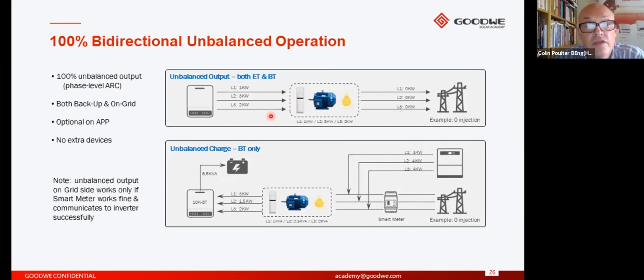If we didn't have the unbalanced load capability, and it was producing a maximum amount of output power, and we have to observe again the fact that we can't export anything to the grid, so we're applying export limitation, then the output of this inverter on each phase would reduce down to 1 kilowatt on each phase. So we'd supply 1 kilowatt to each of the loads here. We'd fully support load 1, which is 1 kilowatt. However, as we're only supplying 1 kilowatt to the loads on phase 2 and phase 3, in order to run these loads, we're now having to purchase power from the grid to be able to support them. So as you can see, it's not very effective. That's why we've introduced the unbalanced load capability.